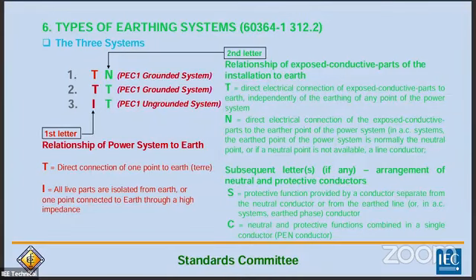Now, you go to the installation. Dalawa kasi ito, yung red, yun yung source, then the installation, papunta na sa installation mo. Then the relationship of exposed conductive parts of the installation to the earth. Kung T yan, it's direct electrical connection of exposed conductive parts to earth independently of the earthing of any point of the power system.